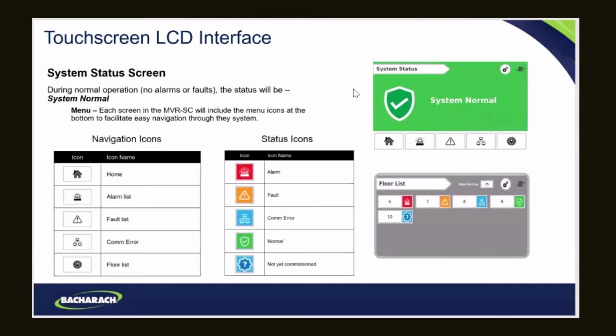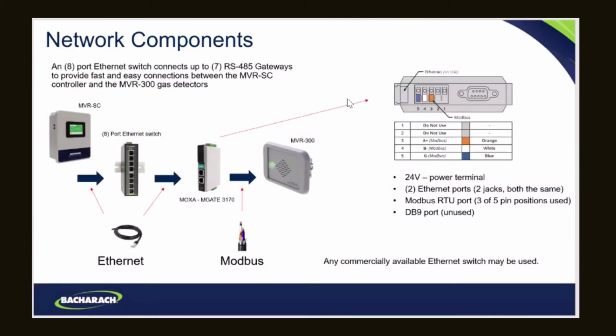Okay, so that's really all the hardware. Let's talk about hardware questions or gaps that I left, or any other questions regarding the connecting parts. On the MVR-300, what's the calibration? How do you do that? How often? Good question. All of these gas detectors come pre-calibrated from the factory. We run them through the test, put sensor elements in, and calibrate them per serial number. So they leave the factory calibrated.